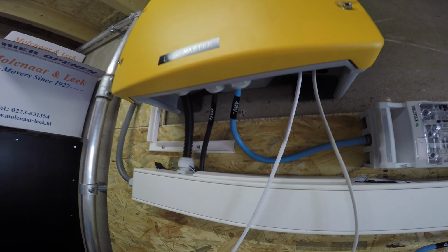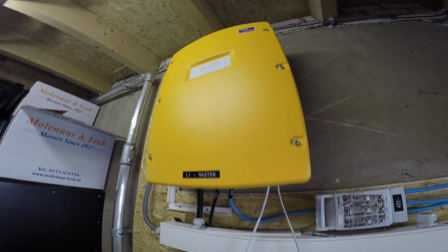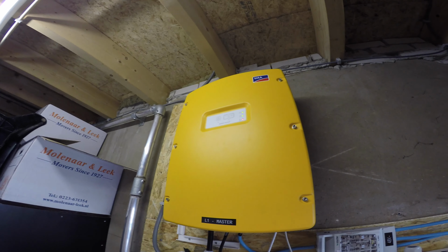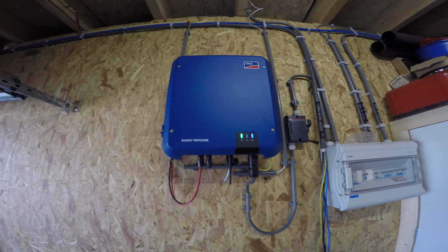Main circuit breaker, 100 amps per Sunny Island. And what you also saw previously on the board was the overarching fuse for the entire system, 300 amps.